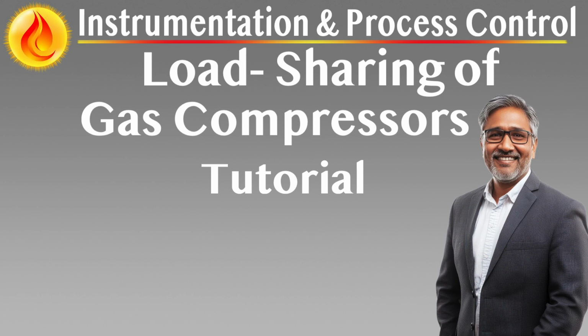Fail-safe and priority logic. Surge protection remains the primary priority. Recycle balancing actions are always secondary to immediate surge prevention logic. If a compressor is at risk of entering surge, it maintains full valve authority regardless of recycle balance status.